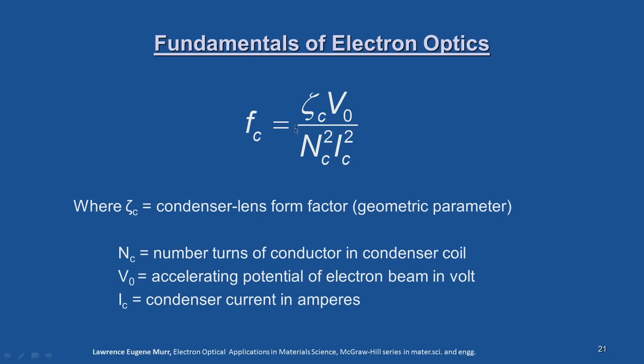The condenser lens serves to regulate the intensity of the electron beam and converge it onto the specimen. The effective focal length is determined by f_c = ζ_c · V₀ / (n_c² · i_c²), where ζ_c is the condenser lens form factor (a geometric parameter), n_c is the number of turns of conductor in the condenser coil, V₀ is the acceleration potential in volts, and i_c is the condenser current in amperes.